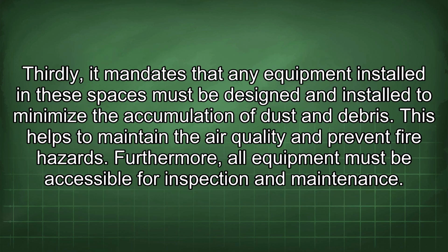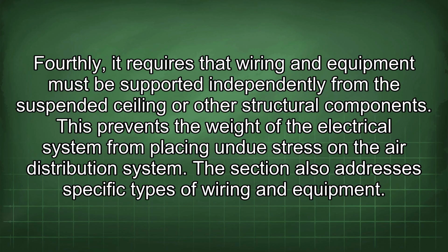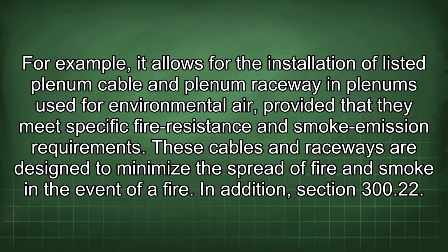Thirdly, it mandates that any equipment installed in these spaces must be designed and installed to minimize the accumulation of dust and debris. This helps to maintain the air quality and prevent fire hazards. Furthermore, all equipment must be accessible for inspection and maintenance. Fourthly, it requires that wiring and equipment must be supported independently from the suspended ceiling or other structural components. This prevents the weight of the electrical system from placing undue stress on the air distribution system. The section also addresses specific types of wiring and equipment. For example, it allows for the installation of listed plenum cable and plenum raceway in plenums used for environmental air, provided that they meet specific fire resistance and smoke emission requirements. These cables and raceways are designed to minimize the spread of fire and smoke in the event of a fire.